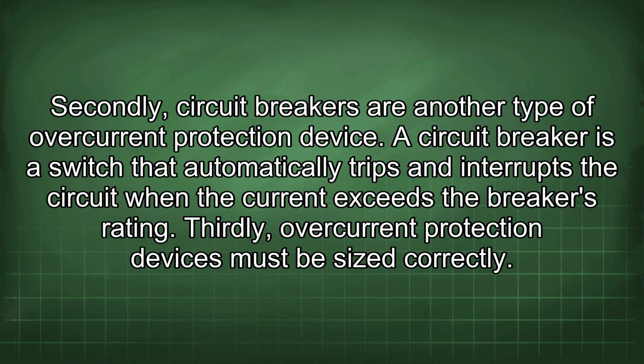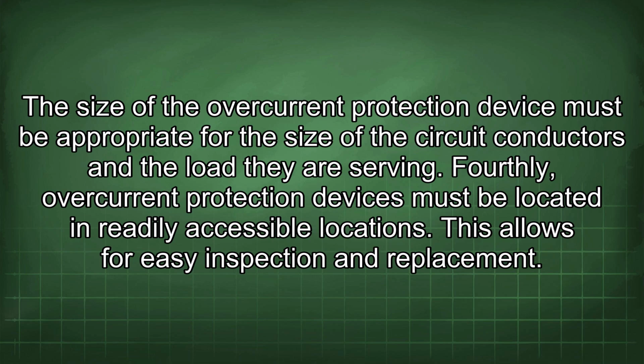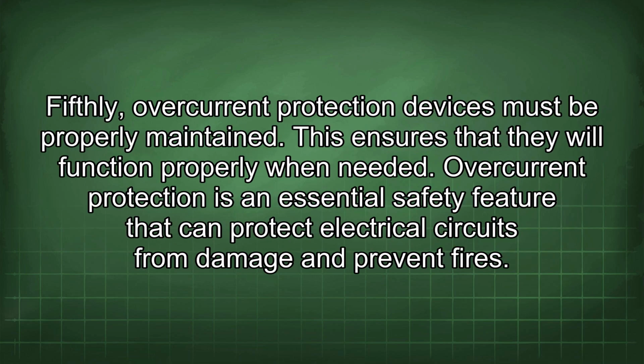Thirdly, overcurrent protection devices must be sized correctly. The size of the overcurrent protection device must be appropriate for the size of the circuit conductors and the load they are serving. Fourthly, overcurrent protection devices must be located in readily accessible locations. This allows for easy inspection and replacement. Fifthly, overcurrent protection devices must be properly maintained. This ensures that they will function properly when needed.